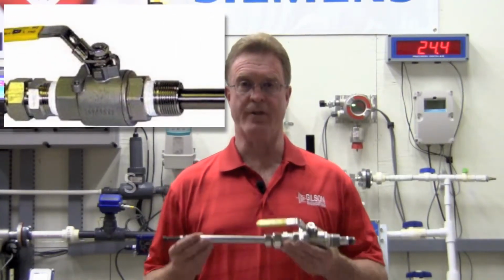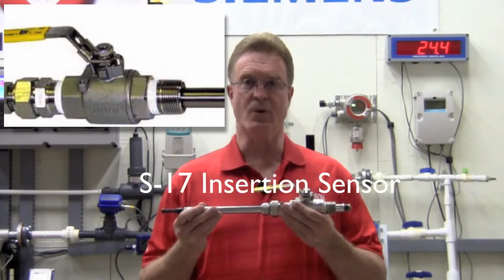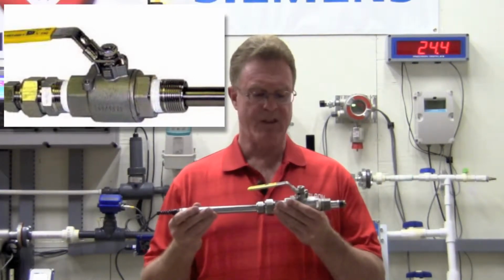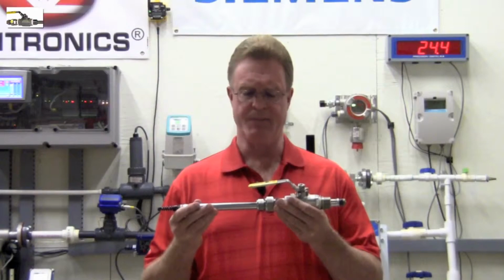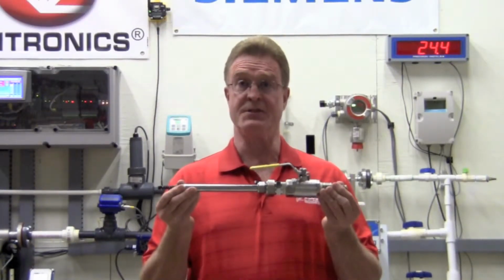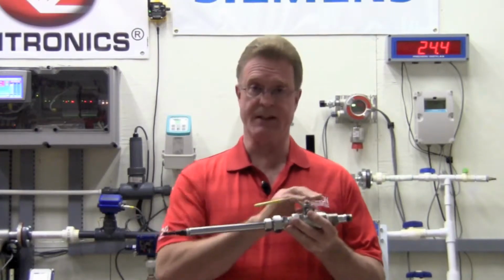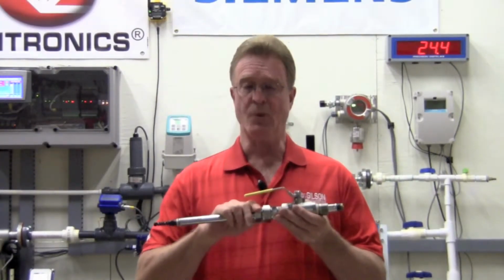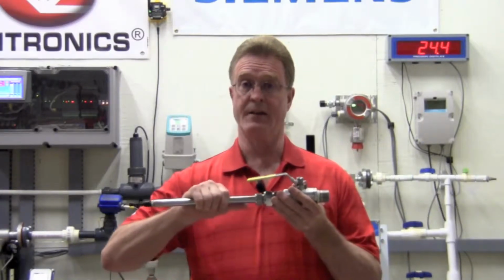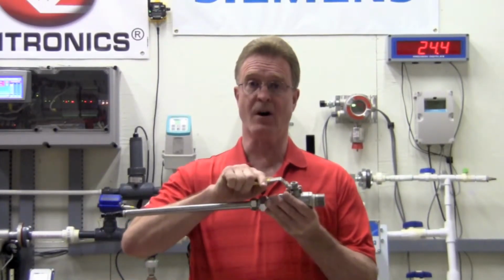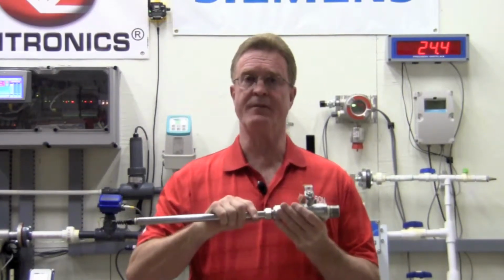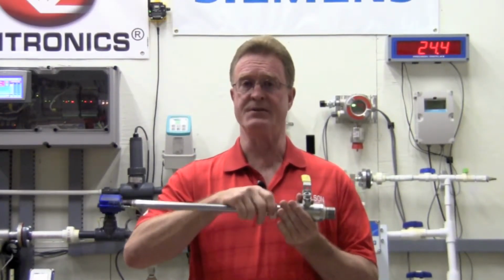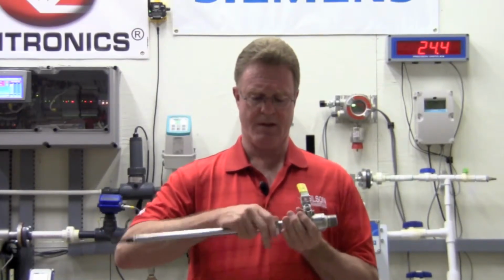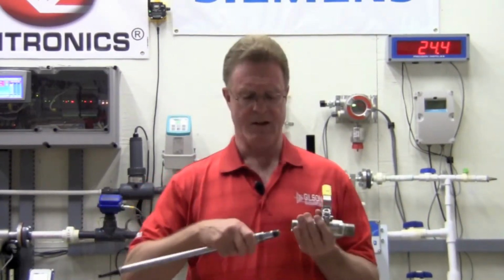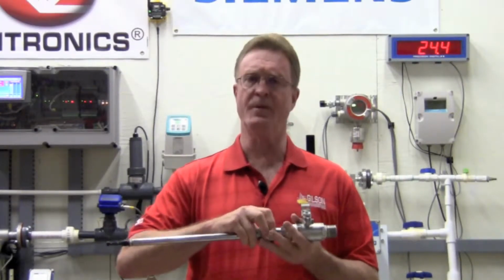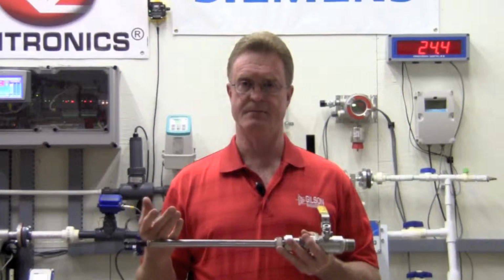The second style of sensor offered from ECD is an insertable valve retraction probe. We have traditionally called this the S17. The S17 is made of a piece of stainless steel tubing, internally amplified, and the electrode on the front, just the same as the S10. But with this assembly, we allow you to extract the sensor, shut a ball valve, sealing you off from the process, allowing you to remove the sensor and accomplish your calibration. Reinsert the sensor, open the ball valve, and you're back in business.